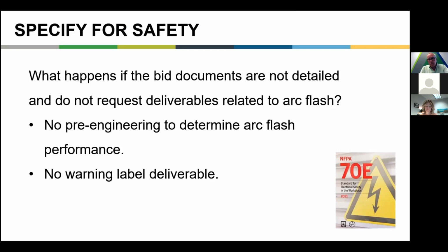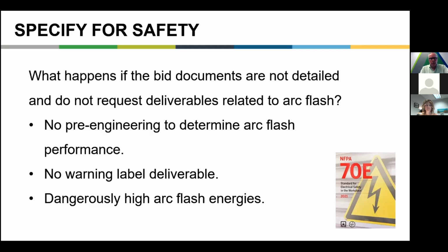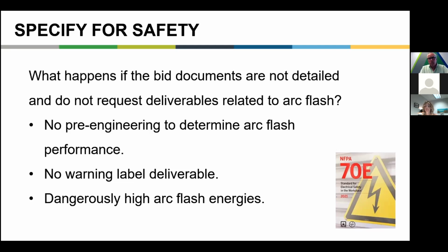No warning label deliverable. So if you don't ask that the arc flash analysis be done and that the consultant or contractor apply labels when they're done with the installation, it won't be done. And it usually results in dangerously high arc flash energies. The way equipment was built and installed decades ago is in some ways maintained today. So you have to design, install, and build differently for arc flash in order to remediate it.